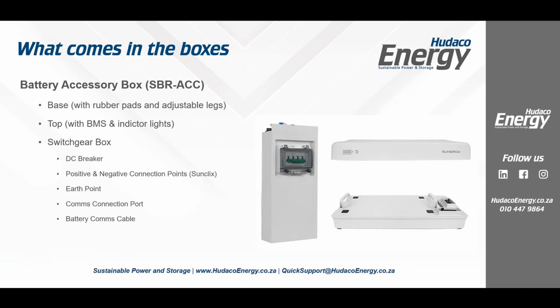This battery is IP55 rated, so it can get splashed. It's no issue. The guys want to raise it off the floor a little bit just in case somebody spills some water on the floor. And you'll see these handles just allow you to take it out of the box very easily. There's also an arrow, and it says on here back and front. So there's really no thought that's required whatsoever.